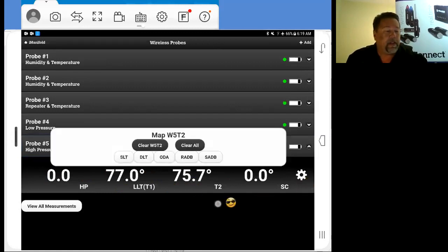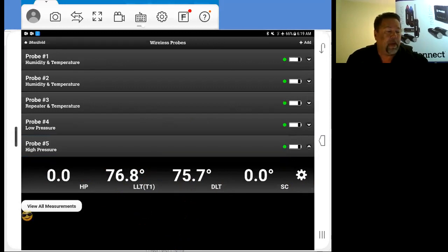And to map that, I just tap the temperature. As you can see, it gives me a menu of what I can map it to. This one, we're going to use discharge line temperature. I map it to DLT. There's my liquid line temp, my discharge line temp, my high pressure, and this would be my subcooling hooked up.